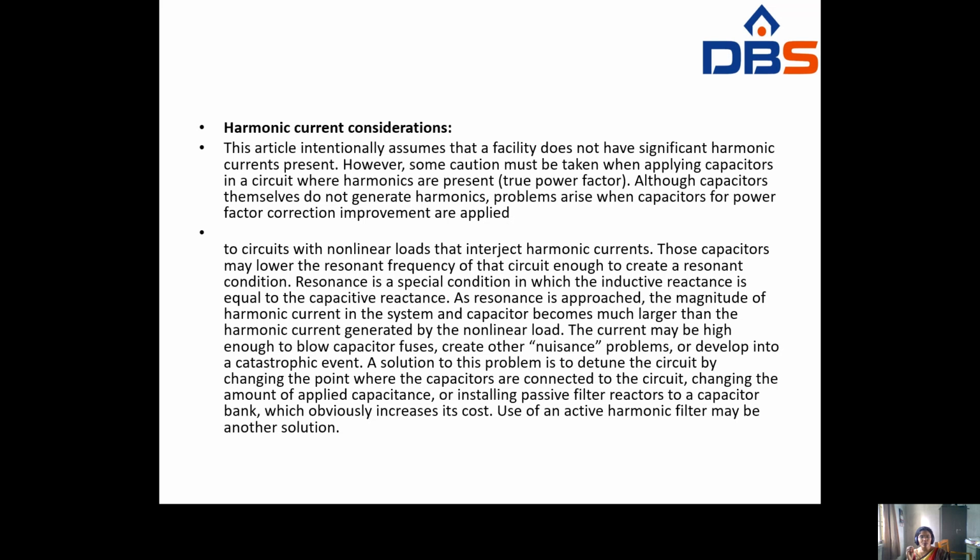Although capacitors themselves do not generate harmonics, problems arise when capacitors for power factor correction improvement are applied to circuits with non-linear loads that inject harmonic currents.